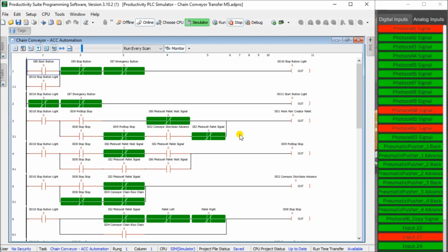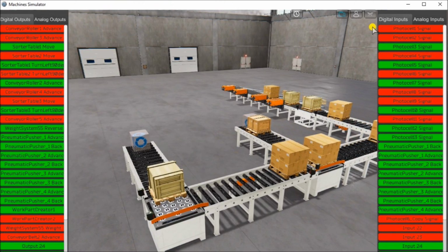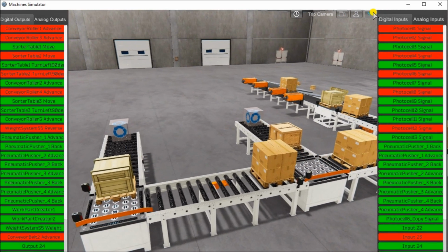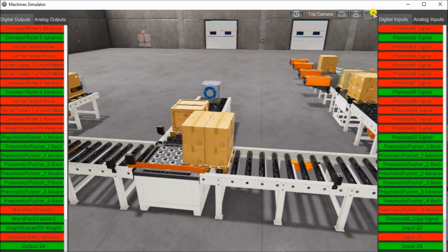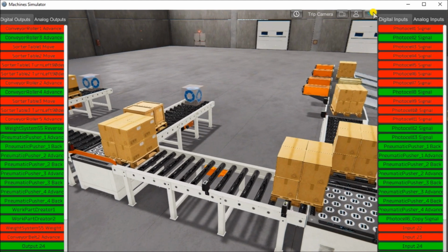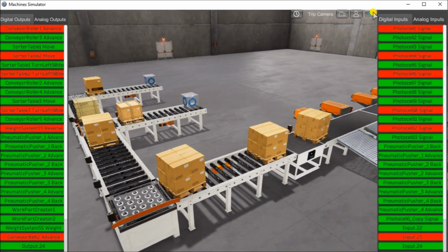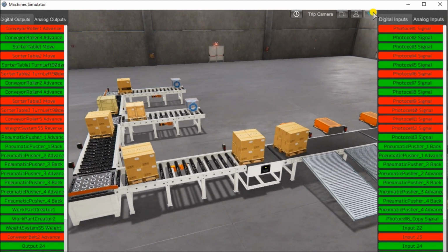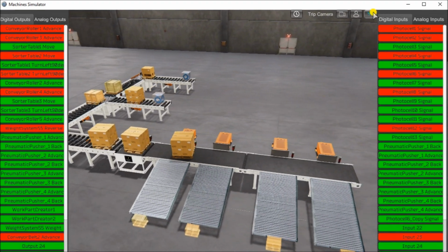Next, and the final step, is developing and testing that program. So test the logic that you developed. Once again, the previous steps are helpful in the process. First, start with what is referred to as ringing out the I/O. This is where you would trigger the inputs and set the outputs to verify the wiring and communication.